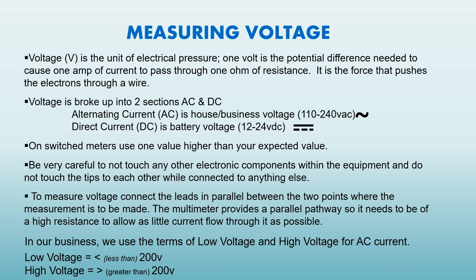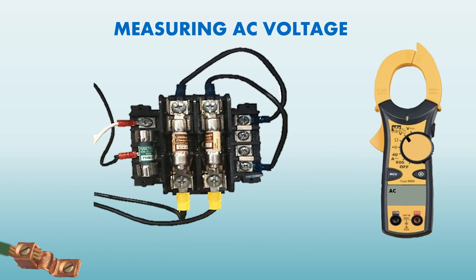In our business, we use the terms of low voltage and high voltage for alternating current. Low voltage is under 200 volts. High voltage is considered 200 volts or higher. When testing alternating current, we set our meter to voltage AC. We use our meter leads to connect our circuit. Here we're testing 208 single phase. Because our circuit is running through fuses, we test the opposite side of our fuses to ensure that our current is flowing through.